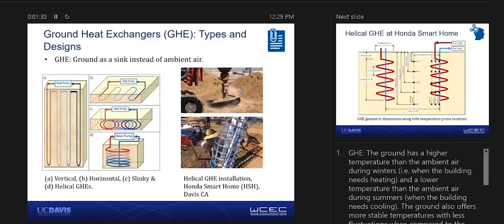The basic principle of a GHE is using the ambient soil or ground as a sink instead of the ambient air. To understand this, let's say we have this nice, cool conference room maintained at 25 degrees Celsius, represented by this cup. The outside air in the summertime, let's say it's 100 Fahrenheit, or 40 degrees Celsius. The heat pump works by consuming electricity and makes the heat transfer from a lower temperature to a higher temperature.